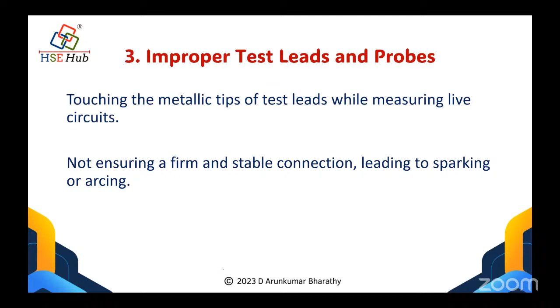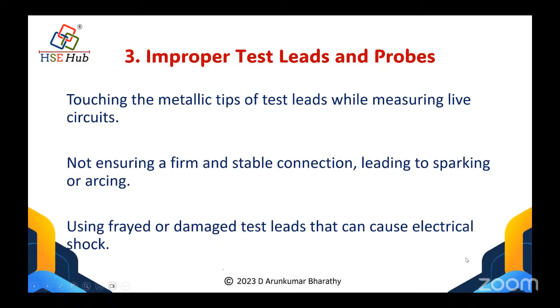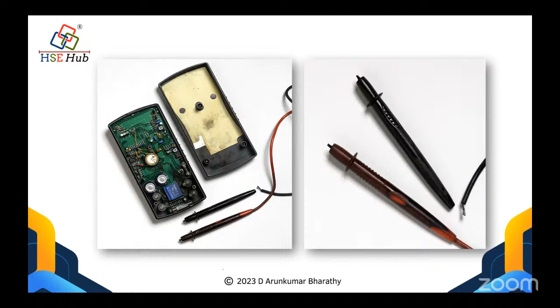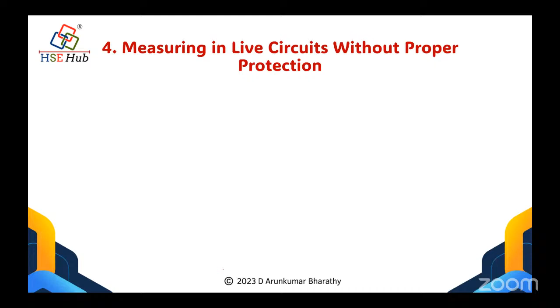So the testing, because see, we are going to measure an electrical live circuit. We need to be safe. What is in between the live circuit and us is only the probe, the testing and measuring equipment probe. When the probe is not selected properly, when it is not handled in the right way, then there is a risk of electric shock or arc, right? Worn out probes, damaged probes, incompatible probes, means there will be a rating and there will be another rating for the probe. So this must be followed very seriously. Then the fourth is, normally it is very rare, but it does happen, measuring a live circuit without proper protection.